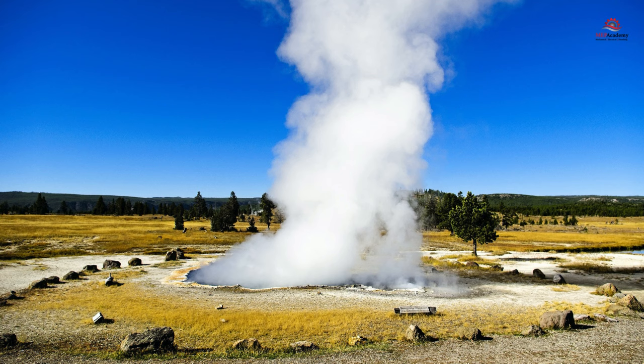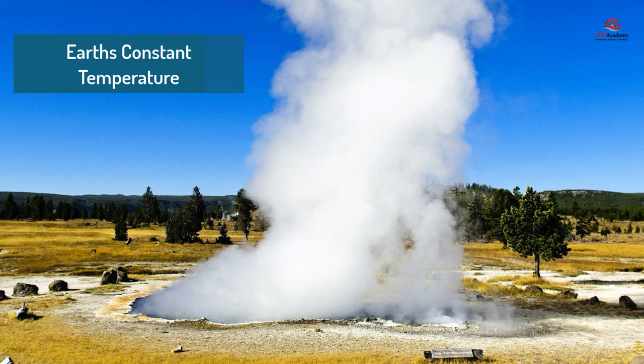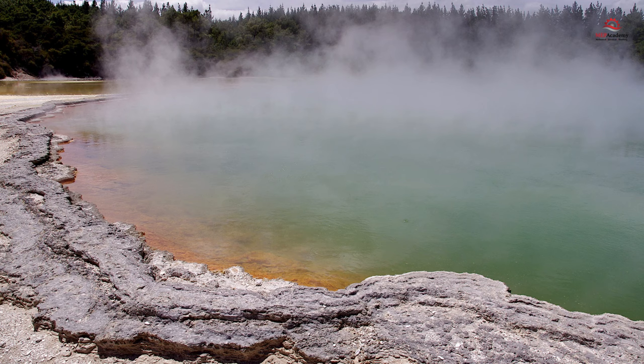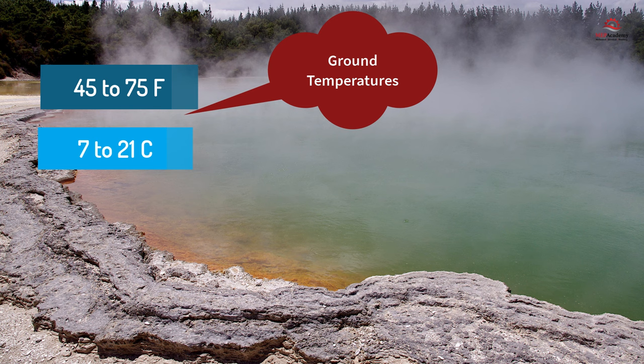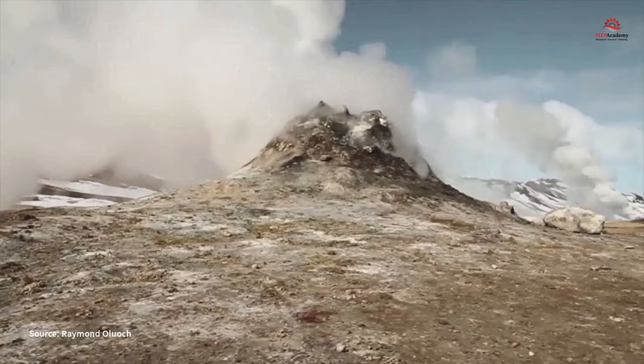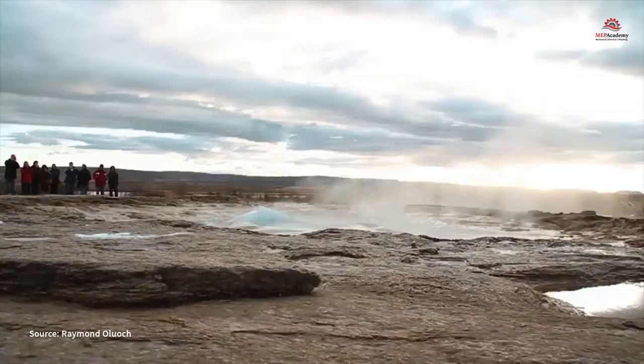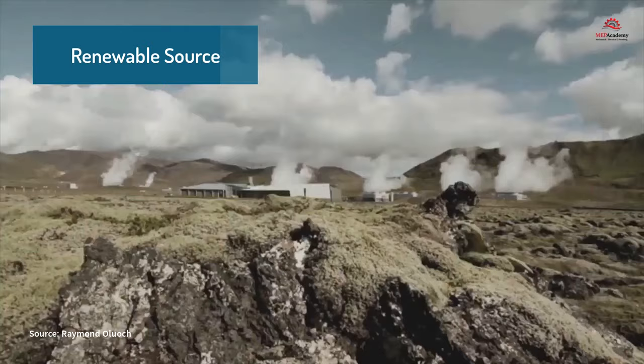The use of geothermal heat pump systems takes advantage of the Earth's relatively constant temperature beneath the surface based on location and depth. The Earth maintains a ground temperature range from 45°F (7°C) to 75°F (21°C). Taking advantage of this natural heat source is what gives the geothermal heat pump greater efficiencies than a standard heat pump, and this source of heat is also naturally renewable, making it a great energy source.